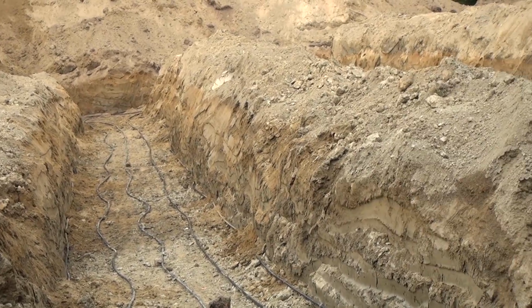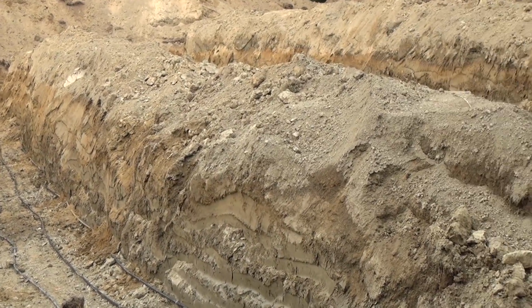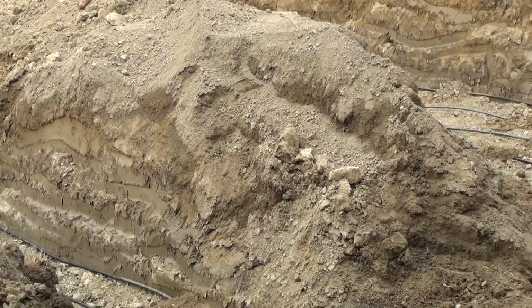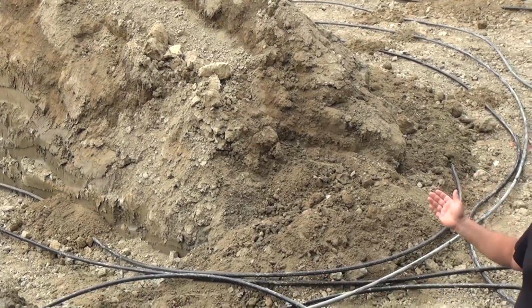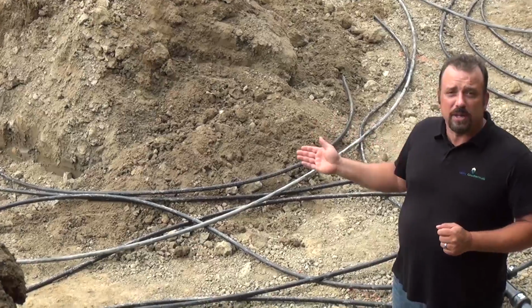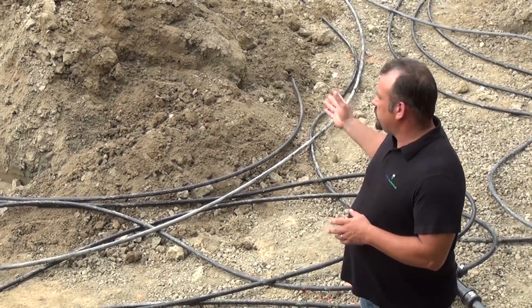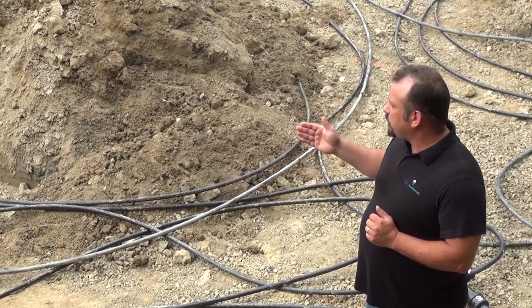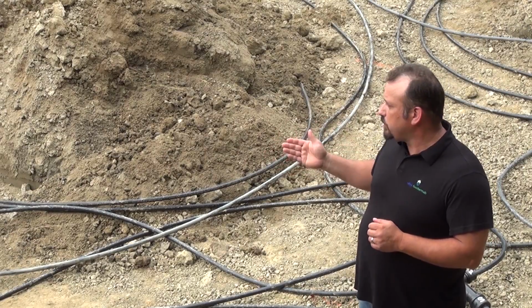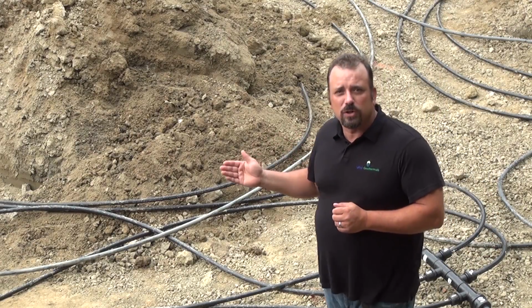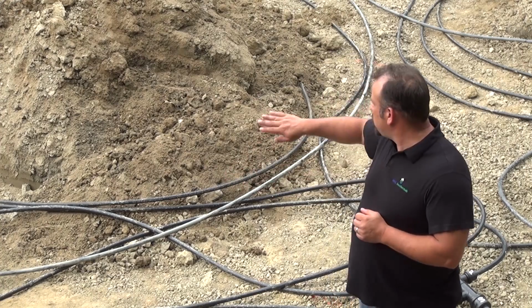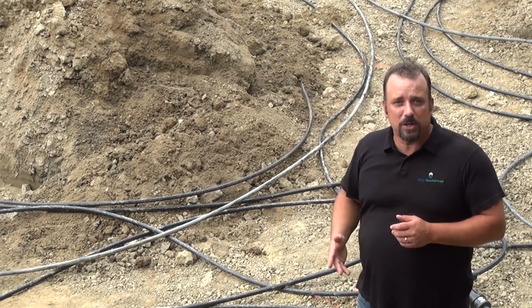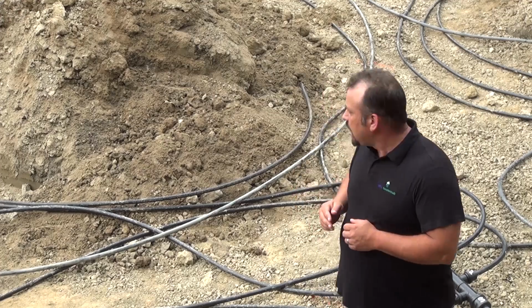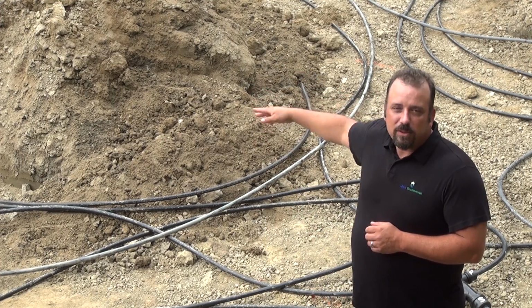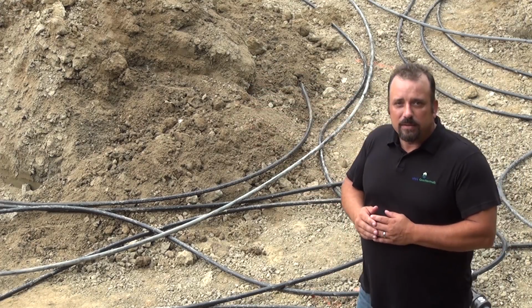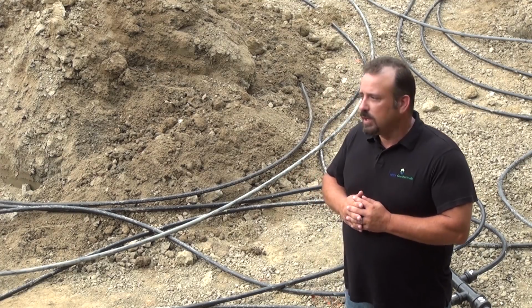Another way you can look at the horizontal system is, if you have this same 5-ton house, which could also have been done here, for the same amount of pipe run we could have used a 55-foot by 100-foot long pit, which means you wouldn't have had trenches. It would have been just one big open pit, much like digging a foundation for your home. The pipe runs could have been laid in and out of the pit with about 20 inches of separation between the loops.